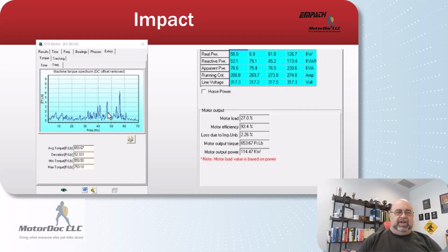The other thing is because the EMPATH is a direct descendant of the Oak Ridge National Labs project, there's a definite torsional-based readout for it. As a part of what they were looking at was motor-operated valve torque. So this is one of our torque readings. We also calculate out not just the air gap torque, and it's different than taking direct shaft torque. That we brought up during another presentation at the conference by somebody else that was doing torque, and somebody said, well, ESA, and I said, well, they're actually different readings.